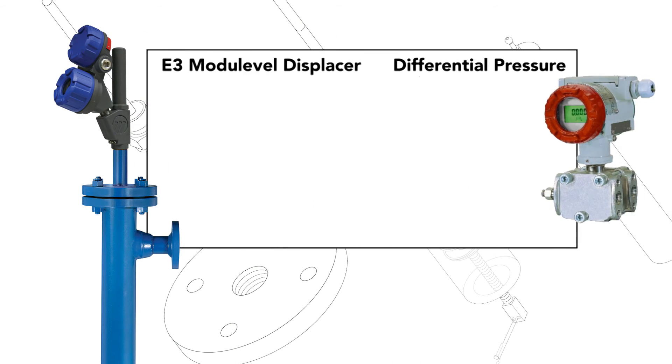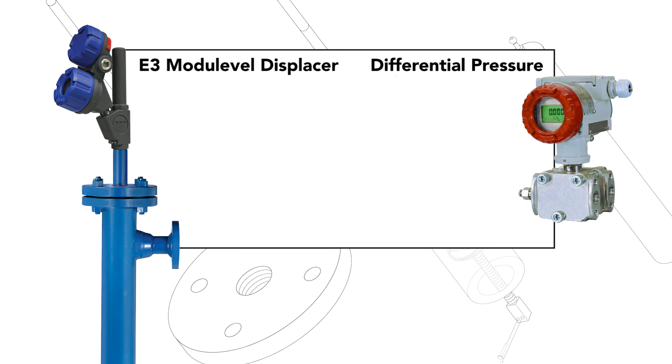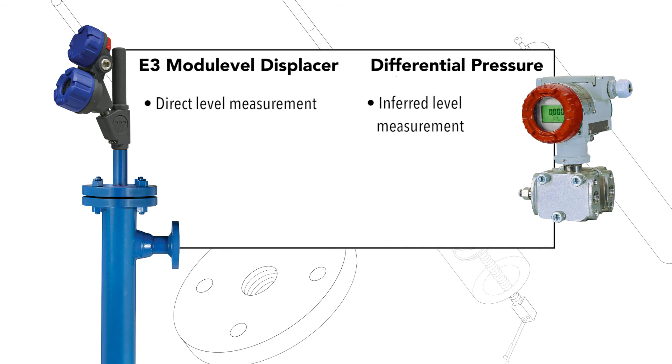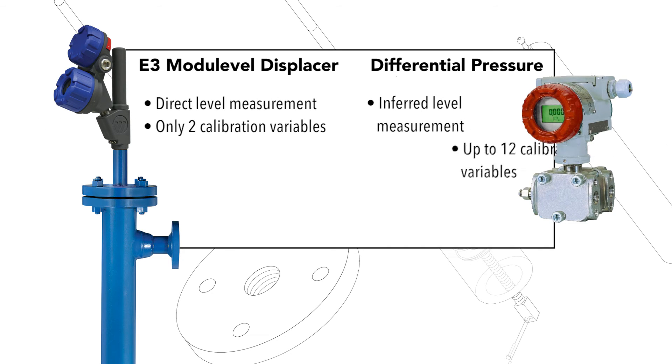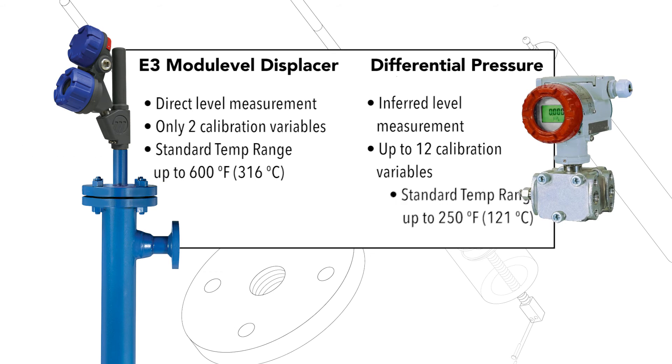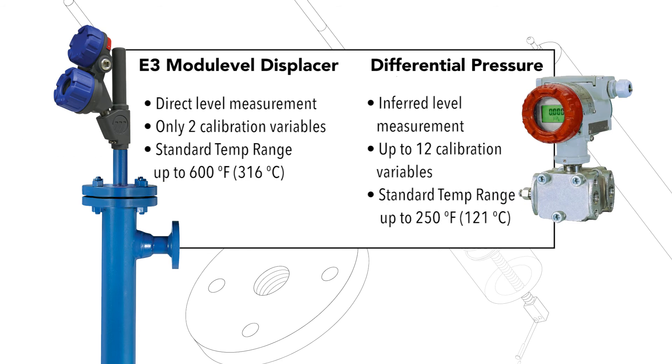E3 Modulevel Displacer transmitters also outperform differential pressure transmitters. They provide direct versus inferred level measurement, require only two calibration variables for proper operation, offer a higher temperature range, and are quickly and easily installed.